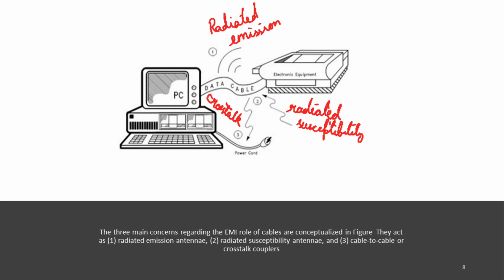So here is an example where you can see how cables are responsible for EMI. A good cable shield will have a low transfer impedance. The effectiveness of the shield also depends on whether or not the shield is terminated, and if so, how it is terminated. Connectors usually are needed to terminate cables. When no cable shields or connector filters or absorbers are used, connectors play essentially no role in controlling EMI. The influence of connector types, however, can play a major role in the control of EMI above a few megahertz. This applies especially when connectors must terminate a cable shield and or contain lossy ferrites or filter pins. Connectors and cables should be viewed as a system to cost effectively control EMI rather than considering the role of each separately, even though each offers specific interference control opportunities.